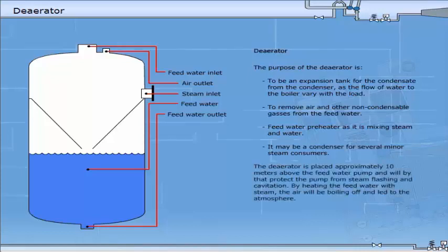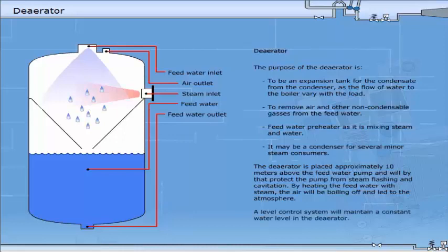The de-aerator is placed approximately 10 meters above the feed water pump and will by that protect the pump from steam flashing and cavitation. By heating the feed water with steam, the air will boil off and be led to the atmosphere. A level control system will maintain a constant water level in the de-aerator.